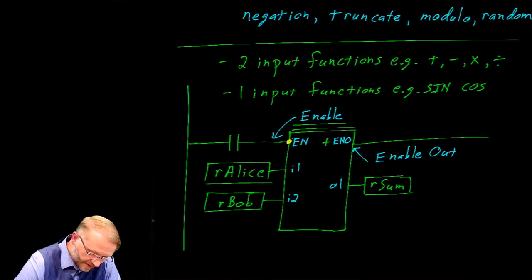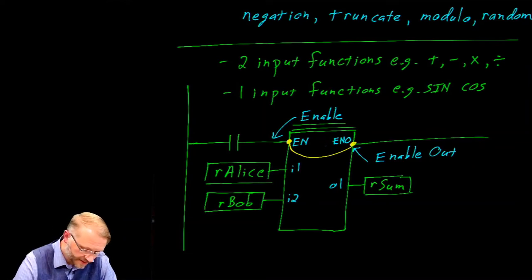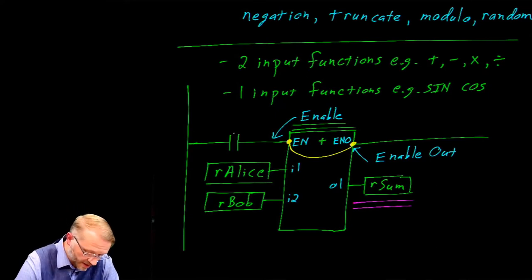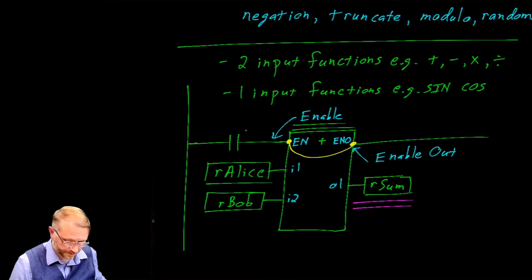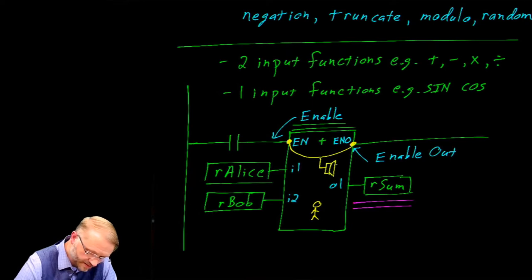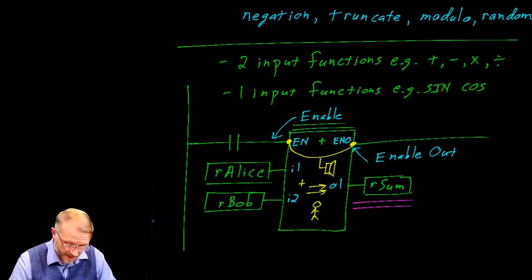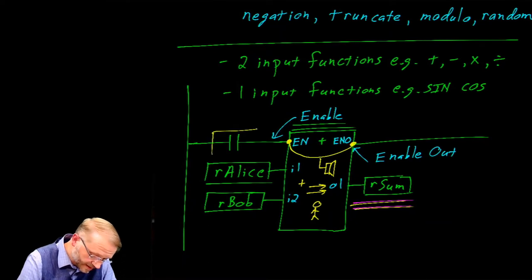There are a few things to bring to your attention. First, you could think of the enable out as a direct connection to enable — just think of it as a wire that goes right through the block. Whatever enable does, enable out will follow. The other thing is that this memory location is only updated when this rung evaluates as true. Think of it this way: inside we have a worker waiting for the alarm to go off. As soon as enable is activated, the worker will take the summation of these two and move it to the output. No enable means no work is done, so we will not write to rsum unless this block evaluates as true.